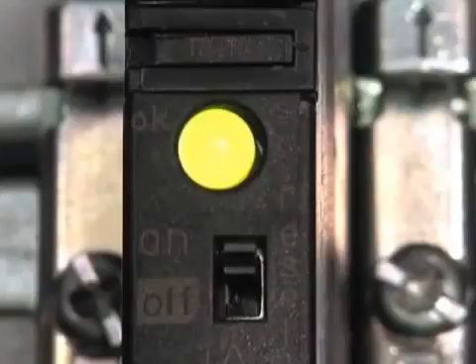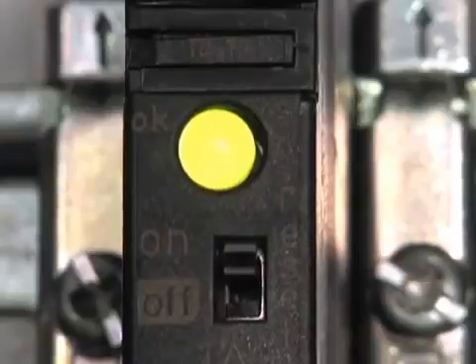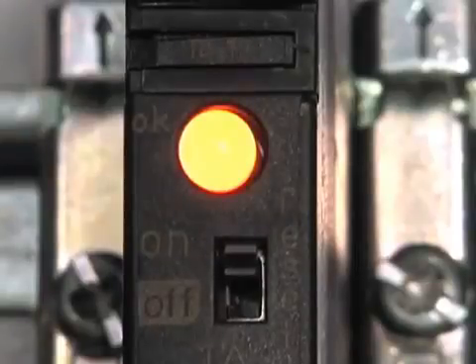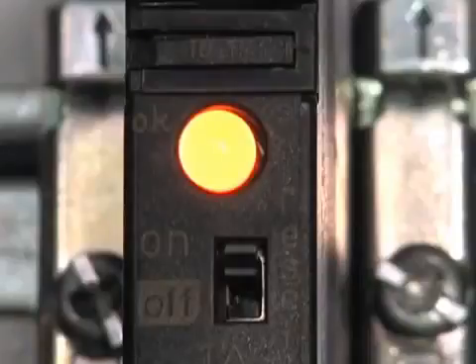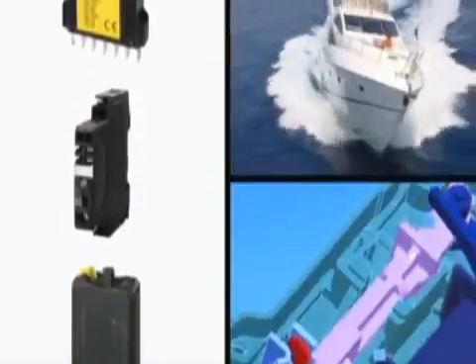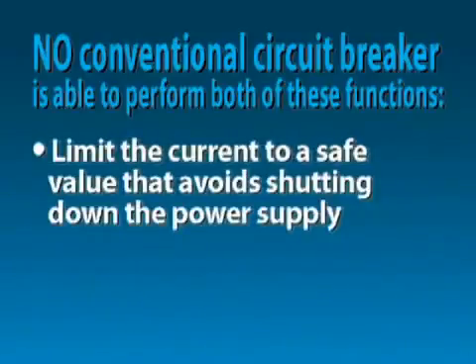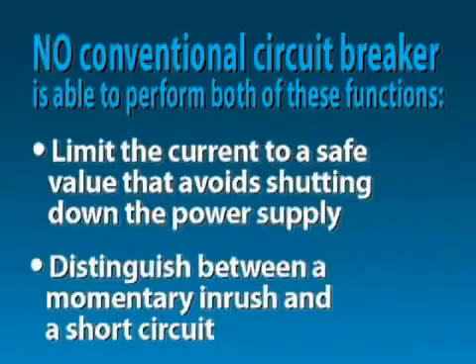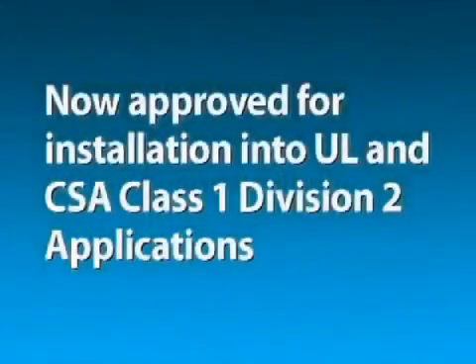The device, through an LED, also lets the user know if an overload is present and when disconnection occurs. This is displayed by an orange LED displaying an overload short circuit, then red LED displaying complete disconnection. Conventional circuit breakers are effective in many applications, but because switch mode DC power supplies are current limiting, no conventional circuit breaker is able to perform both functions, limit the current to a safe value that avoids shutting down the power supply, and distinguish between a momentary inrush and a short circuit. Now approved for installation into UL and CSA Class 1 Division II applications.